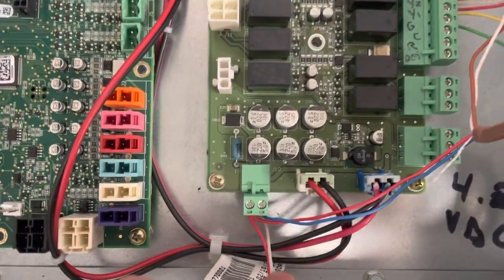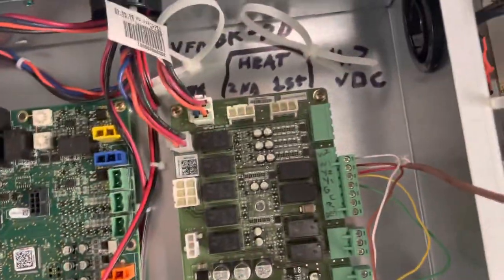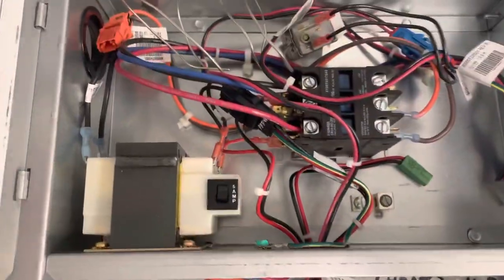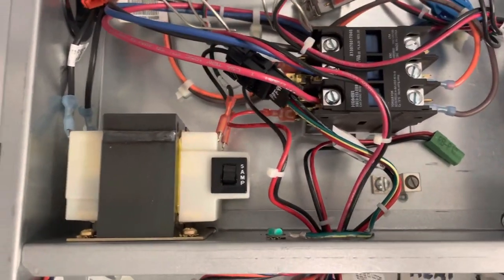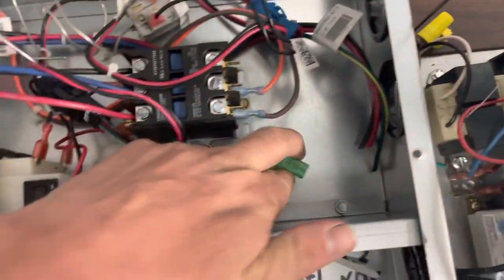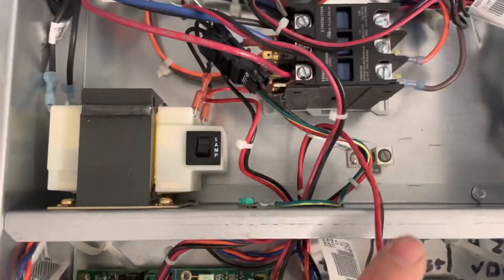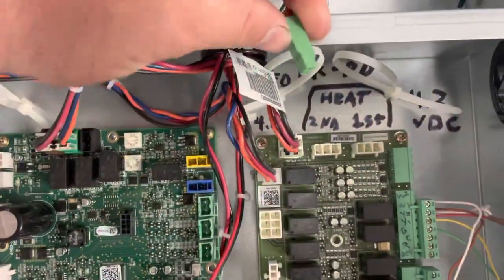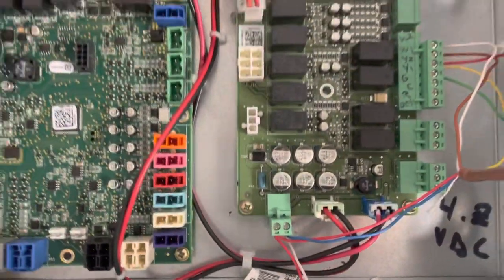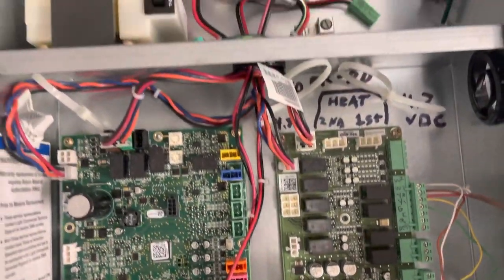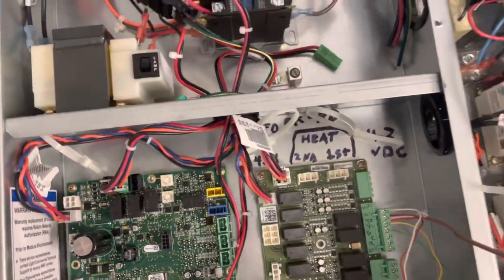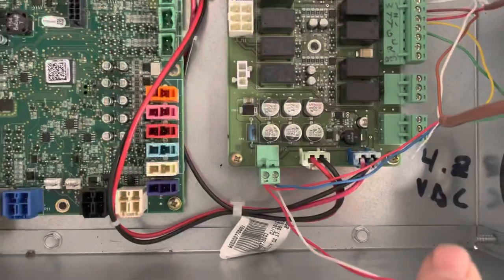Actually, this unit, seven and a half ton, comes with a transformer installed. And this plug right here, if you trace that out, that green plug, it would tie in here. So that's how it comes from the factory for the seven and a half ton. I'm just mimicking that because I have a 110 transformer in my outdoor unit.